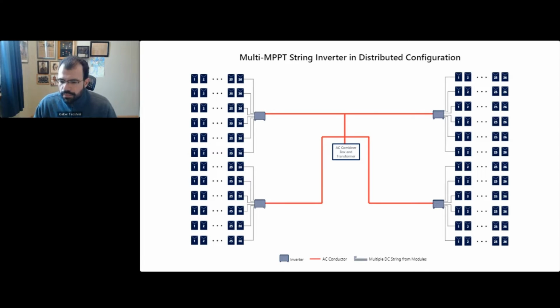First, I'm showing here the multi-MPPT string inverters, okay? In this configuration, the inverters are distributed throughout the array. While this reduces DC balance of system costs, it increases AC BOS costs and AC losses due to the long AC wire runs. Additionally, as the DC to AC ratio increases, this configuration will experience greater losses as it cannot take advantage of the free voltage drop that is possible during times of clipping. Another disadvantage is the higher cost of communication circuits to the inverters because the inverters are spread across the array. Okay? The advantage of this configuration is that it allows for increased energy harvest due to the number of MPPT per inverter. Okay? So that's the multi-MPPT string inverter flavor.